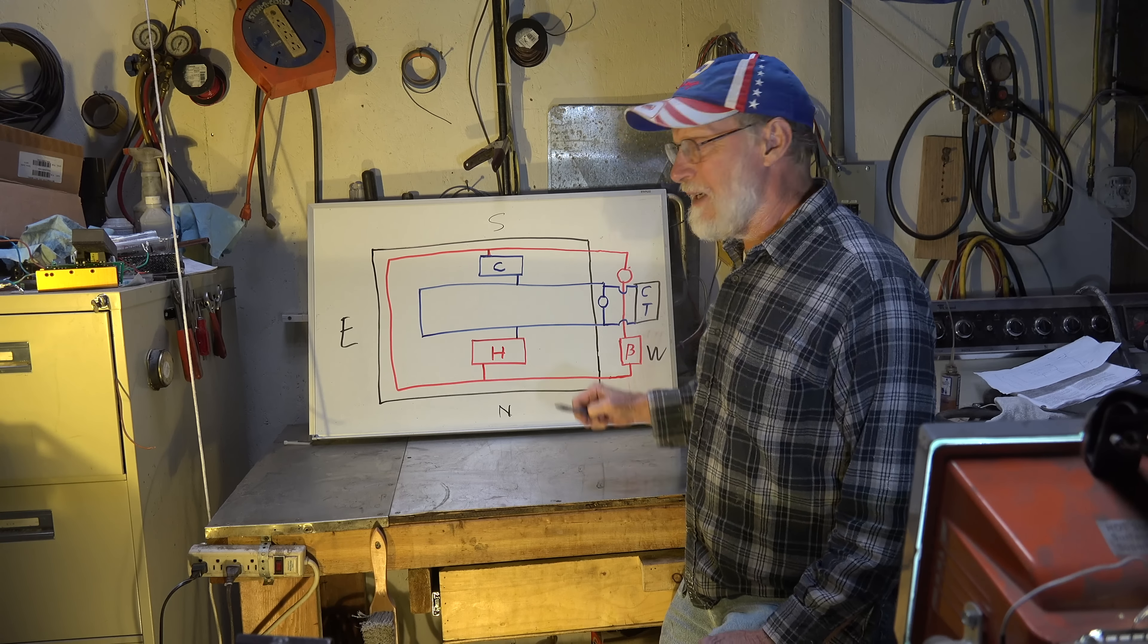Down here I have another heat pump, just like the other one, but it's in heat. So what it's going to do is take that warm water that's cycling about here, that has the heat that came off of this. It's going to run it through the evap of this heat pump in heat. It's going to cool it off and run it into this cool pipe.